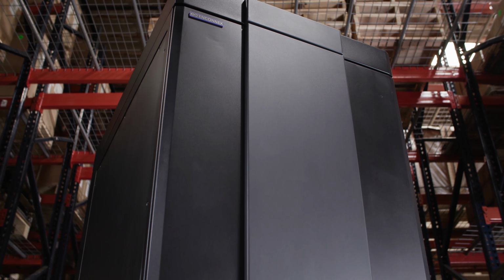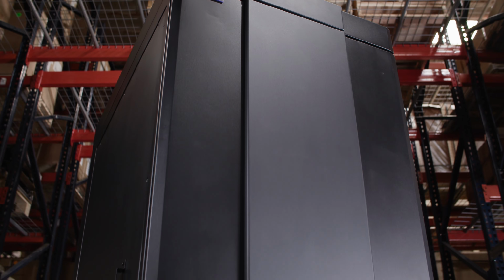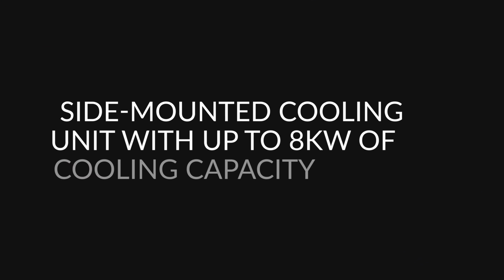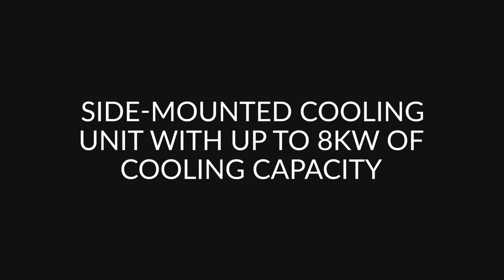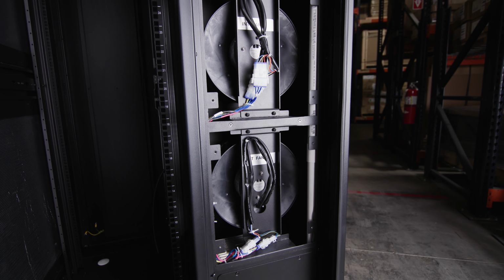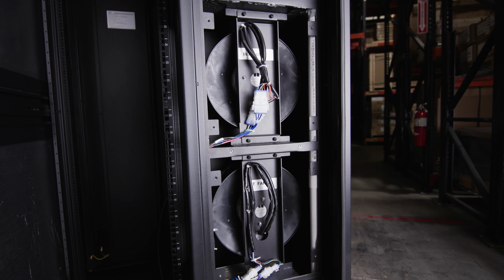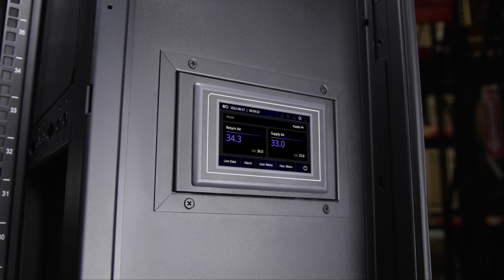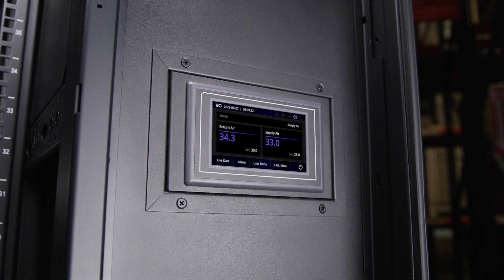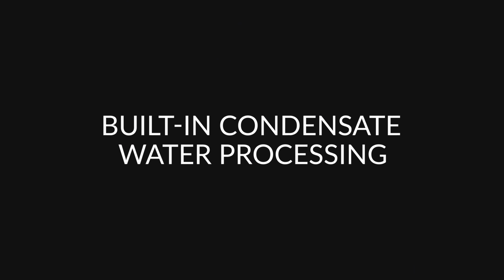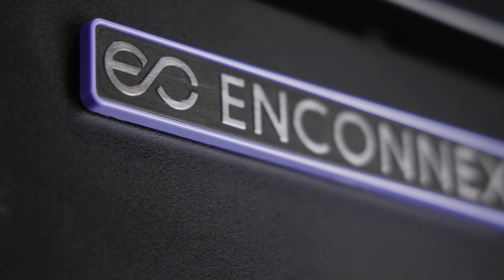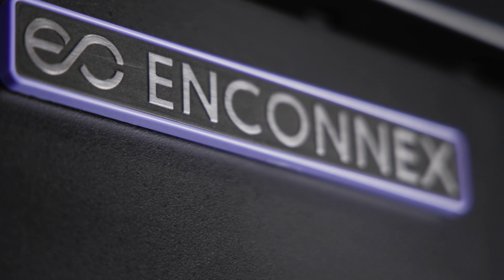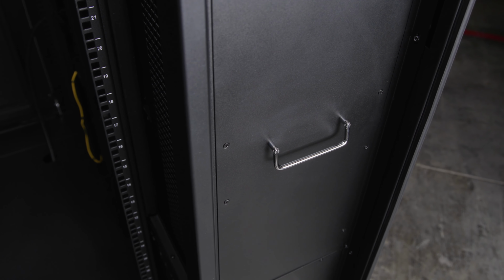The 8M is the only 42U microdatacenter cabinet on the market with a self-contained, side-mounted cooling unit offering up to 8 kilowatts of cooling capacity. This integrated, highly efficient cooling unit is equipped with a 4.3-inch display for quick user interface and system monitoring. The built-in condensate water processing device eliminates the need to attach water drainage pipes, enabling fast and easy deployment.